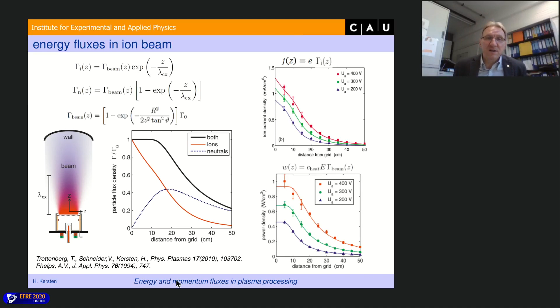the axial ion current profile by the Faraday cup, and you can really see this profile. It's really by the ions. But if we measure with our thermal probe the power density, then we get such a profile. And this is the profile of both, of the ions and the neutrals. So this is really a very nice method.